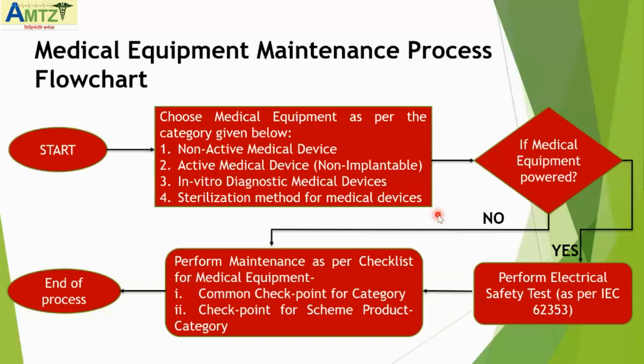Now this is the medical equipment maintenance process flow chart. First we start, and we have to select where the device belongs, whether it is in the four main categories: non-active medical device, active medical device non-implantable, in vitro diagnostic medical device, or sterilization method for medical device. Once you place the device, first we have to understand whether the device is powered or not, whether any electrical supply is coming or not. If it is powered, then it has to undergo the electrical safety test as per IEC 62353. That is the International Electrotechnical Commission standard 62353. It is actually the standard for recurrent tests and tests after repair of medical electrical equipment.